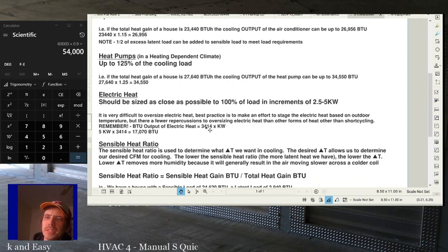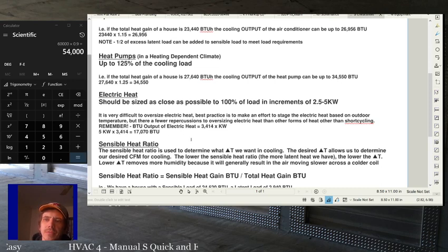So remember, BTU output of electric heat is 3,414 per kW. So either 3.414 times every watt or 3,414 BTUs per kW. All right. So every 5 kW is about 17,070 BTUs. So 5 kW times 3414 equals 17,070 BTUs. So if you want to shortcut it, you can just say 5 kW is 17,000 BTUs, every 5 kW I have in there. So 10 kW is going to be 34,000 BTUs basically, and so on and so forth.